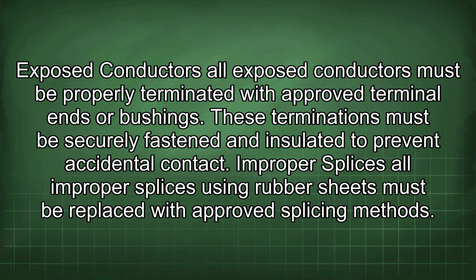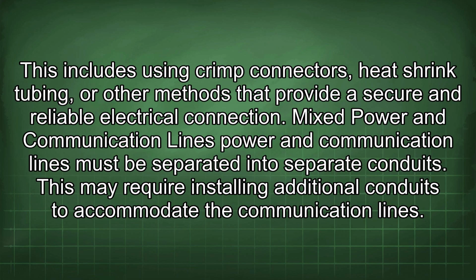Improper splices. All improper splices using rubber sheets must be replaced with approved splicing methods. This includes using crimp connectors, heat shrink tubing, or other methods that provide a secure and reliable electrical connection. Mixed power and communication lines. Power and communication lines must be separated into separate conduits. This may require installing additional conduits to accommodate the communication lines.